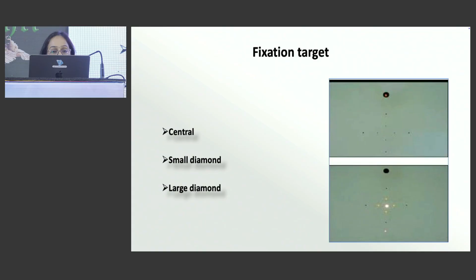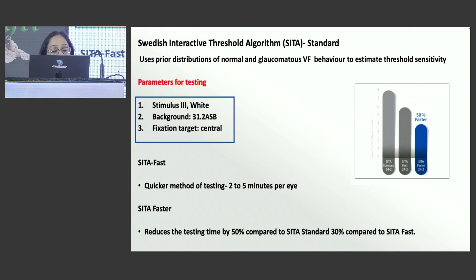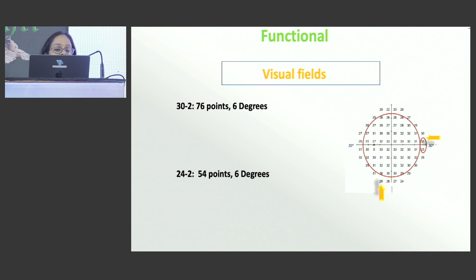And usually we use SITA standard, Stimulus 3 white with fixation target center. You have other options like SITA fast, which is a quicker method, and also even SITA faster method. So you do what usually is a 30-2, which tests 76 points, and then 24-2, which we usually do in glaucoma, which tests 54 points, 6 degrees apart.